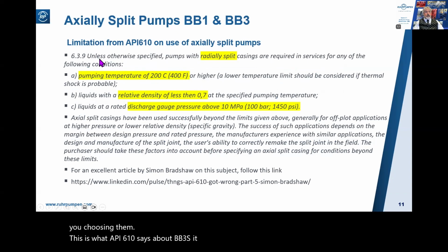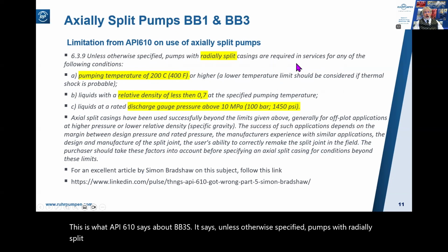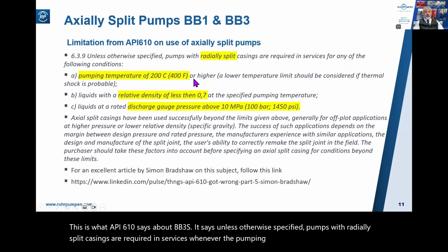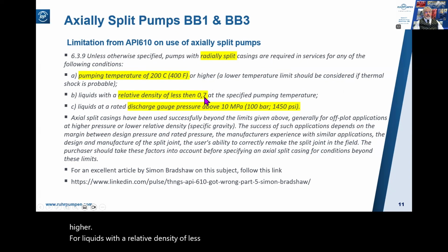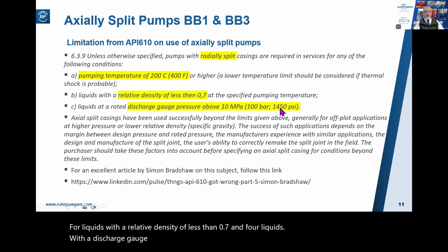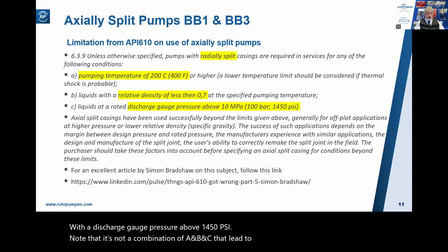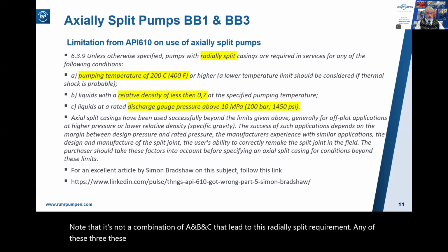It says, unless otherwise specified, pumps with radially split casings are required in services whenever the pumping temperature is 400 Fahrenheit or higher, for liquids with a relative density of less than 0.7, and for liquids with a discharge gauge pressure above 1450 psi. Note that it's not a combination of A and B and C that lead to this radially split requirement. Any of these three triggers the requirement.